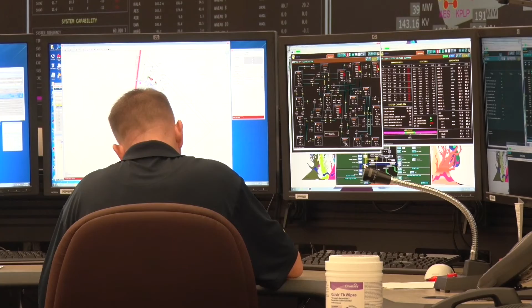motor-operated switches in our existing power lines in the vicinity of the Army bases, which will allow us from system operations to establish this microgrid to provide power to the Army directly. There's been a lot of really good work by Energy Delivery to put that plan together and to enable these SCADA-controlled, motor-operated switches to be installed and make sure that it's all going to work when it's called upon to do so. So the power plant is a major part of it, but the work that's being done by Energy Delivery is critical to the success of this project.